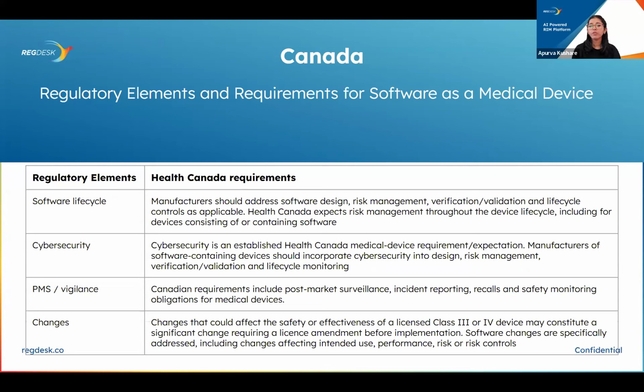And then we will talk a little bit more about the software lifecycle, cybersecurity, PMS, and also the changes that could affect the safety and effectiveness. So, in terms of software lifecycle, it is important for manufacturers to address the software design, risk management, verification, validation, and lifecycle controls as applicable. Health Canada expects risk management throughout the device lifecycle, including for devices consisting of or containing software. In terms of cybersecurity, it is also established in the Health Canada requirements, and manufacturers of software-containing devices should incorporate cybersecurity into design, risk management, verification, validation, and lifecycle monitoring. Then we'll also talk about PMS and vigilance. So Canadian requirements include post-market surveillance, incident reporting, recalls, and safety monitoring obligations for medical devices.